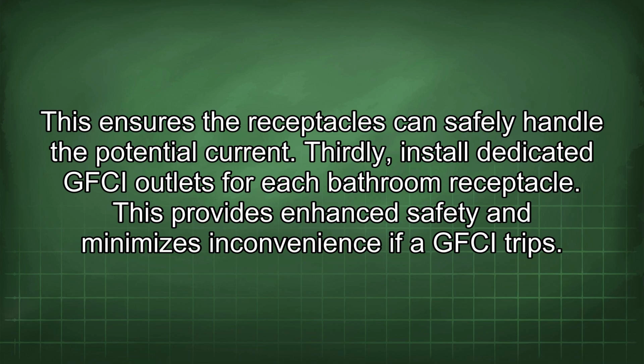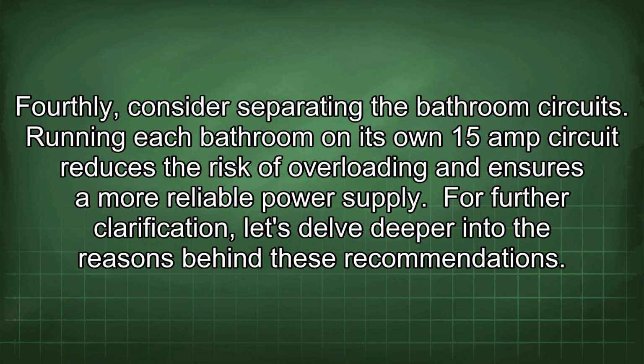Thirdly, install dedicated GFCI outlets for each bathroom receptacle. This provides enhanced safety and minimizes inconvenience if a GFCI trips. Fourthly, consider separating the bathroom circuits. Running each bathroom on its own 15 amp circuit reduces the risk of overloading and ensures a more reliable power supply. For further clarification, let's delve deeper into the reasons behind these recommendations.